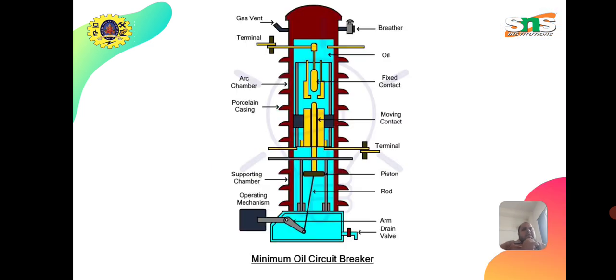This is the structure of the minimum oil circuit breaker. You could see that the level of oil used in the circuit breaker is comparatively less than in the previous type. Here also the fixed contact and moving contact are submerged in the oil, but the chamber is somewhat narrow so that the oil level is reduced. The points marked are the gas vent terminal, arc chamber, porcelain supporting chamber, and the operating mechanism for moving the fixed contact and moving contact. There is a drain at the bottom to refuel the oil, then rod, piston, terminal, moving contact, fixed contact, and oil. Finally there is a device called a breather, which allows air to flow inside the oil circuit breaker.